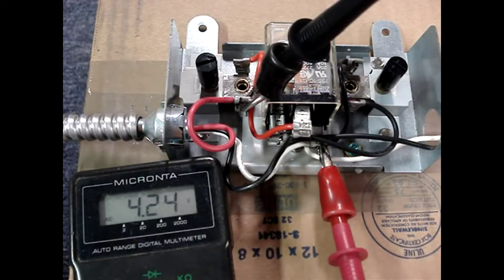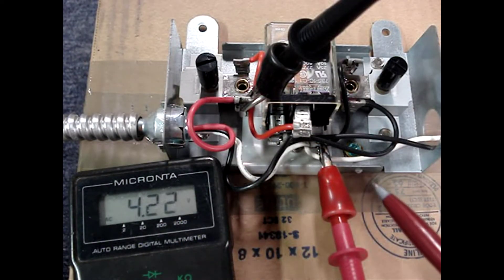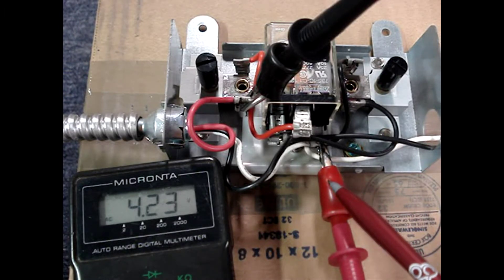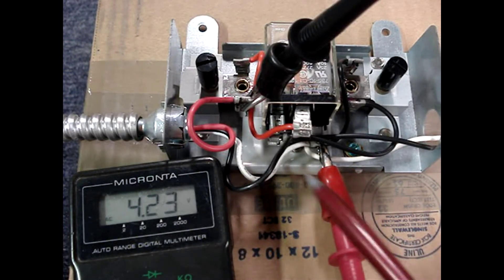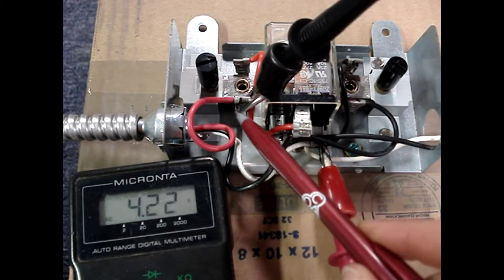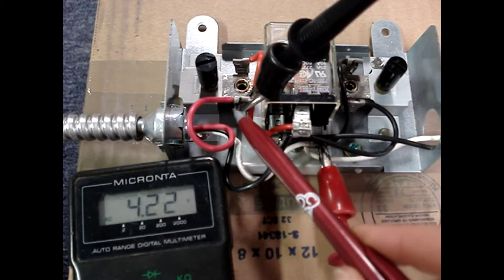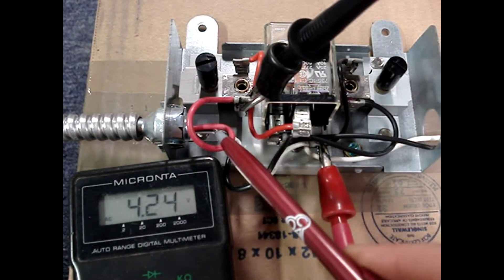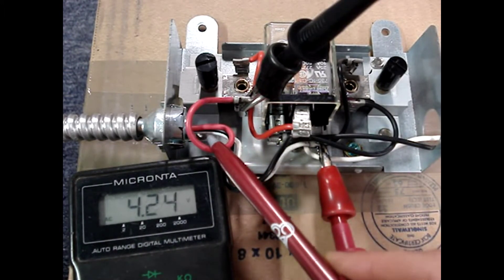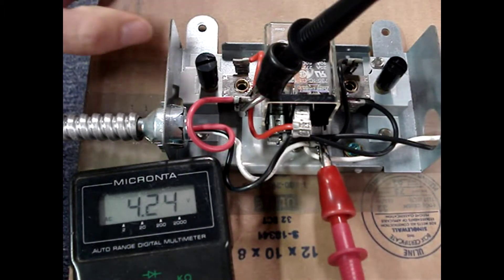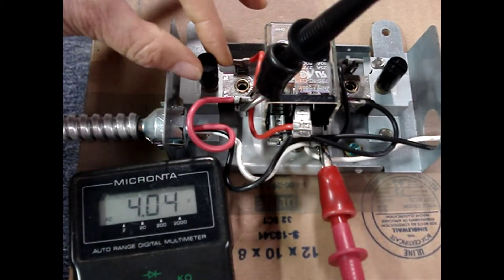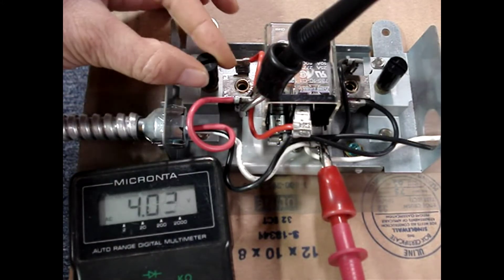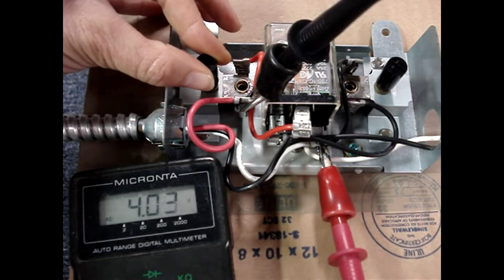I now have the controller energized. I have a multimeter set up to read AC volts. I'm clipped on to the neutral wire and I'm clipped on to the output of the low temperature switch that connects to our low speed fan connection. And I'm going to turn the temperature down to simulate a 90 degree temperature.